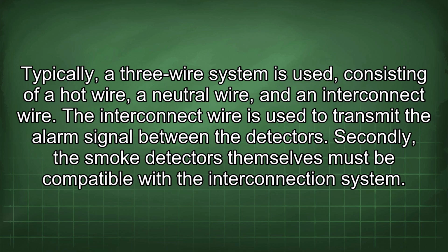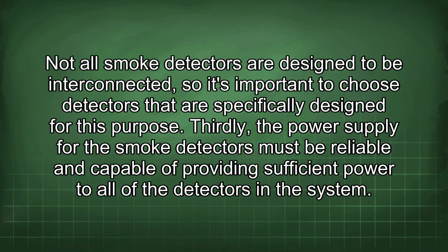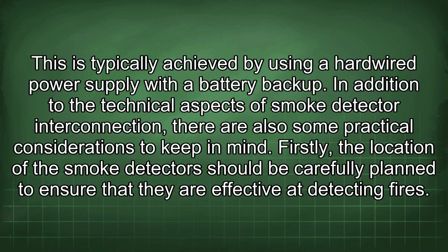Secondly, the smoke detectors themselves must be compatible with the interconnection system. Not all smoke detectors are designed to be interconnected, so it's important to choose detectors that are specifically designed for this purpose. Thirdly, the power supply for the smoke detectors must be reliable and capable of providing sufficient power to all of the detectors in the system. This is typically achieved by using a hardwired power supply with a battery backup.